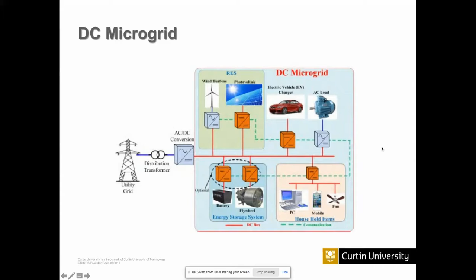So just a couple more slides. What is the advantage of DC? There is no skin effect. The current can flow through the entire cable, not only the outer edges. This will minimize the loss. There is no need for synchronization, and as I mentioned, you can just connect. The beauty of DC is that if you just adjust the voltage, the current can flow from higher potential to lower potential, so there is no reactive power control, no angle control, nothing.